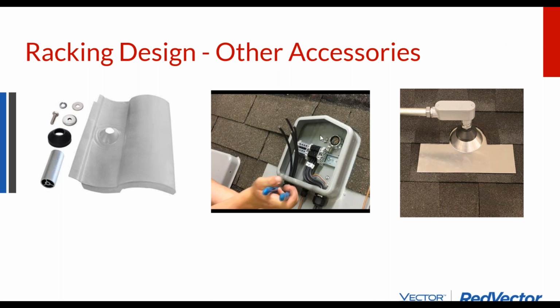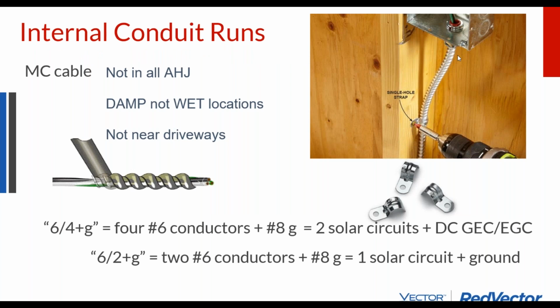So here's the junction box, and we're good. This is a specialty junction box. This is something you could do with more generic material. And the reason you use the specialty box is it gives you a little bit less clearance. But now we're going into the roof here. And this is that MC cable. It's called metal clad cable. And what I do is number 8 is the smallest allowable equipment ground for solar. And so I'll use number 6 MC cable because it has that number 8 ground that's already included and protected. And the MC gives you the metal protection.